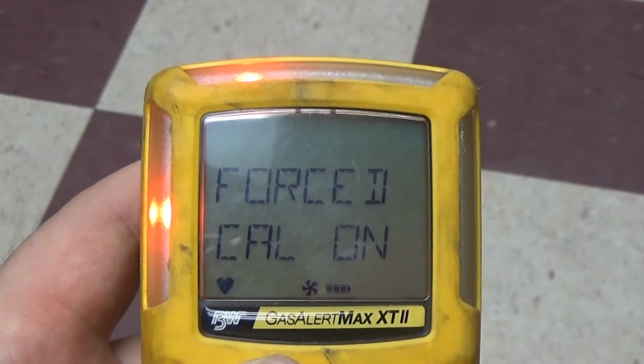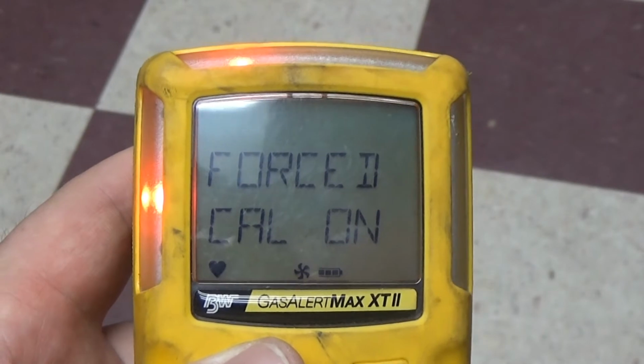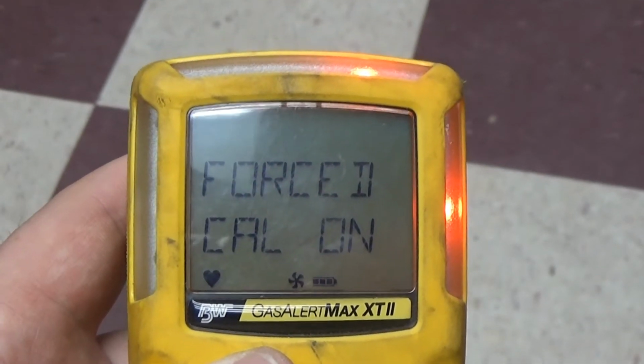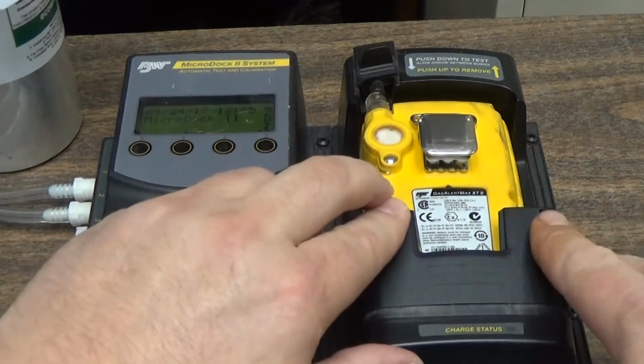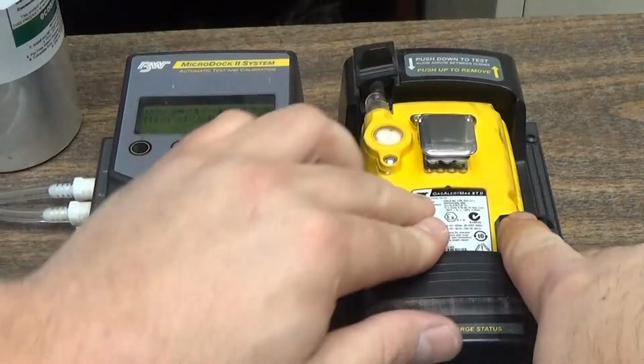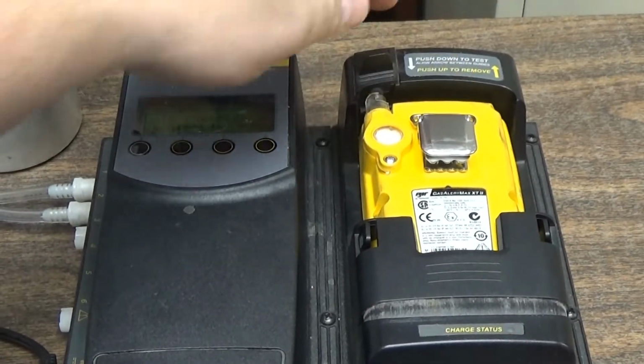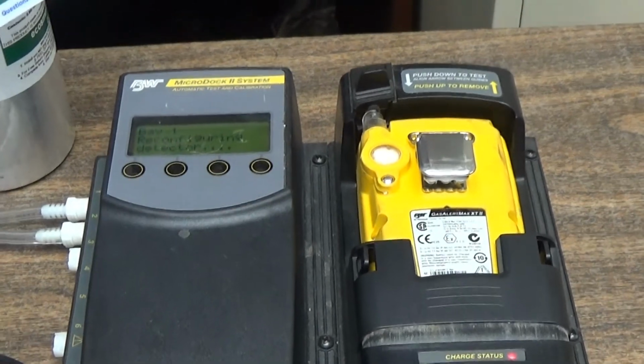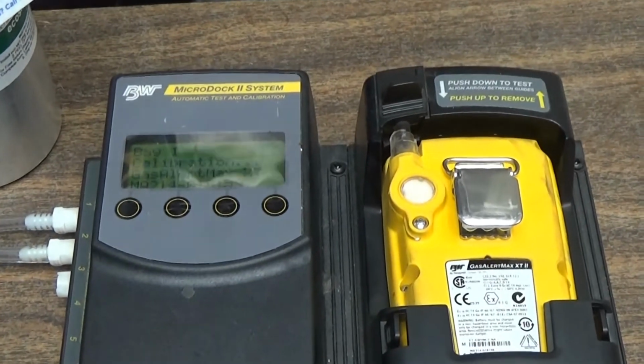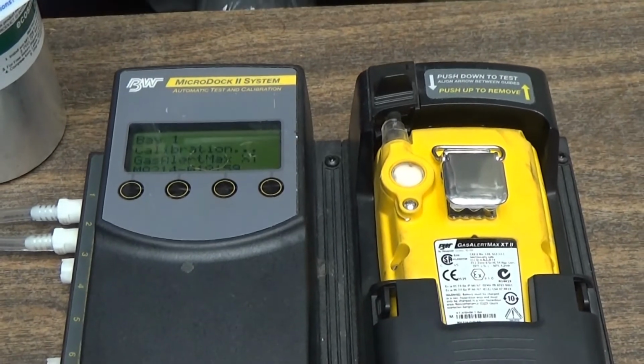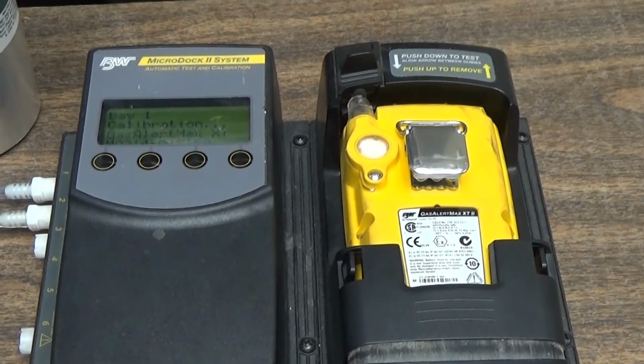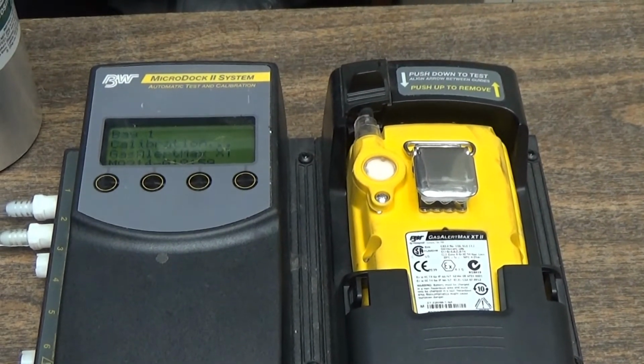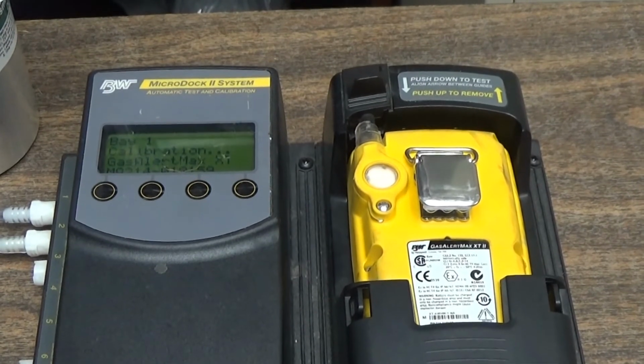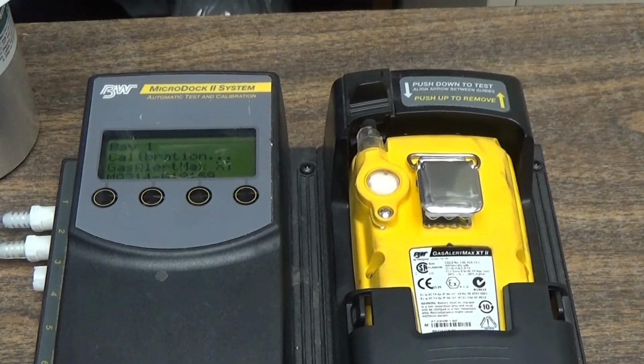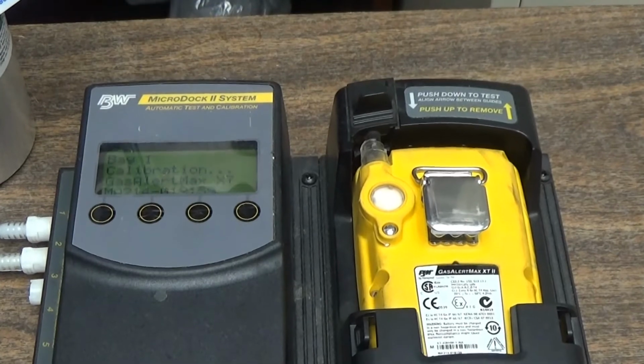At this point, you're now ready to drop it back into the bump station. Insert the meter into the gas bump station, close the lid, pull down the gas chamber, and it automatically starts the calibration. The calibration takes a little bit longer. Generally it takes 3 to 4 minutes to complete a full calibration. Let it run its course until it comes up and shows you on the screen.